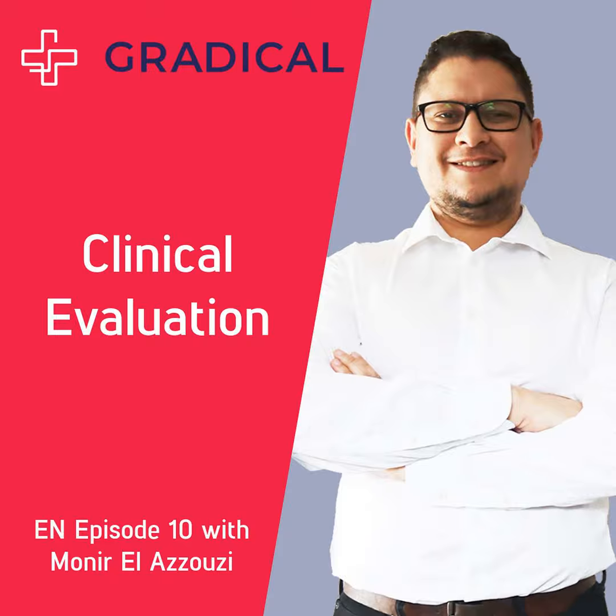So here you have really two separate things: clinical investigation on one side, clinical evaluation on the other side, are really two different things, and the clinical investigation feeds the clinical evaluation. So what you are doing is that you then have to start to create. You have to follow one standard. The standard is ISO 14155, which is a standard that explains the different steps to follow for a clinical investigation.